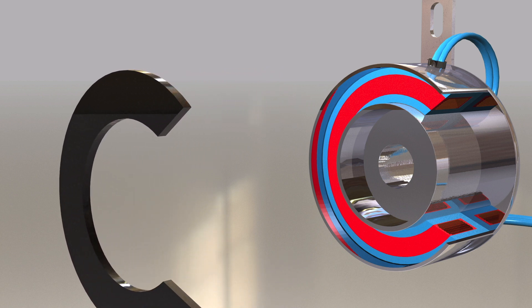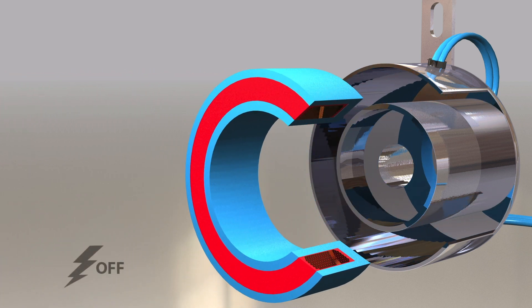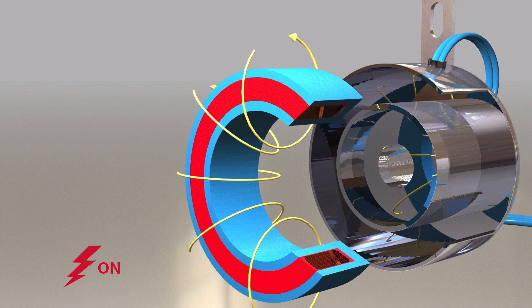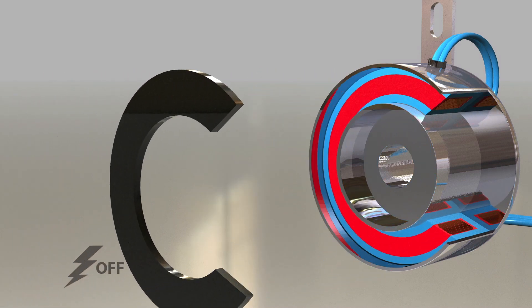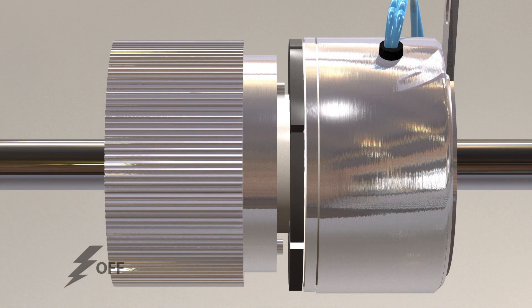Electromagnetic clutches operate via an electric actuation but transmit torque mechanically. When voltage or current is applied to the clutch coil, it becomes an electromagnet and produces magnetic lines of flux. This flux is then transferred through the small air gap between the field and the rotor. The rotor portion of the clutch becomes magnetized and sets up a magnetic loop that pulls the armature against the rotor.